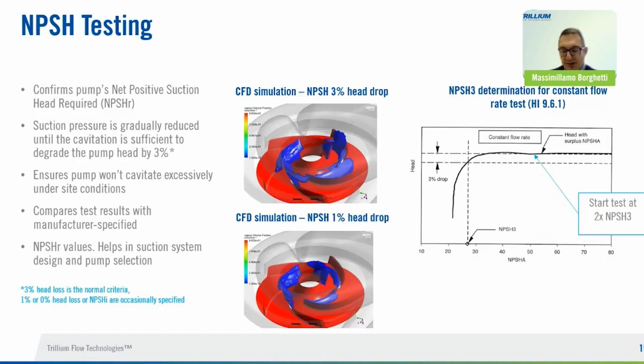Okay, now we move to a very important test that is the verification of the NPSH. That is necessary to confirm the net positive suction head that is required. One of the most visible effects of cavitation is the degradation of the performance due to the presence of the vapor phase that is induced by cavitation. The definition of the required NPSH of a pump is the NPSH available that is able to cause the total head to be reduced, generally by 3%, due to the flow blockage from cavitation vapor in the impeller vanes.